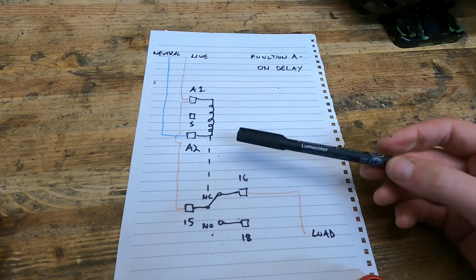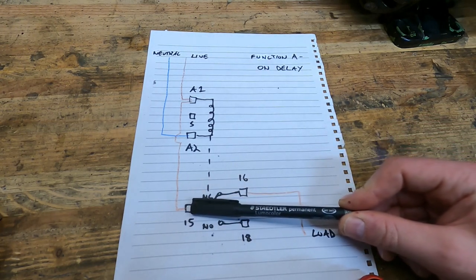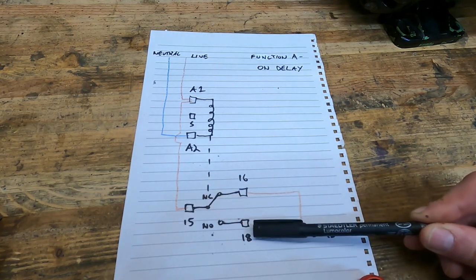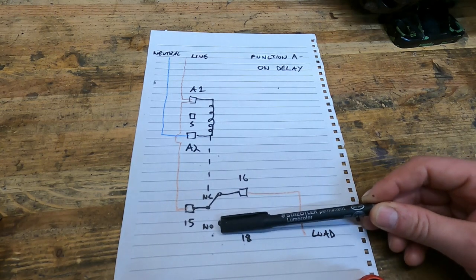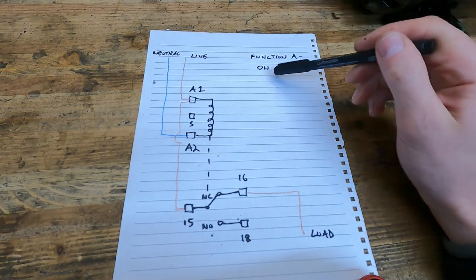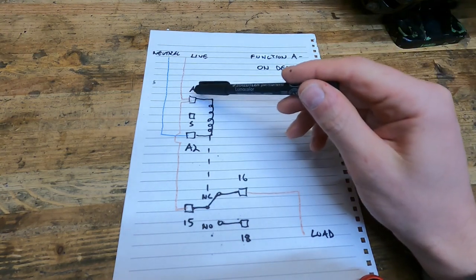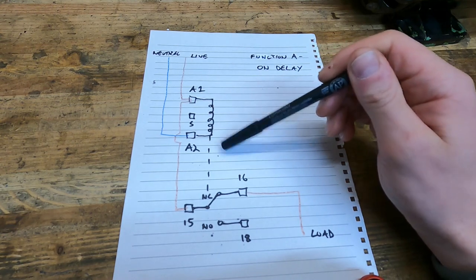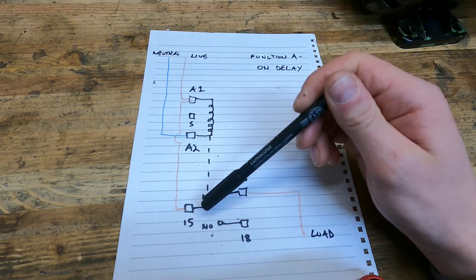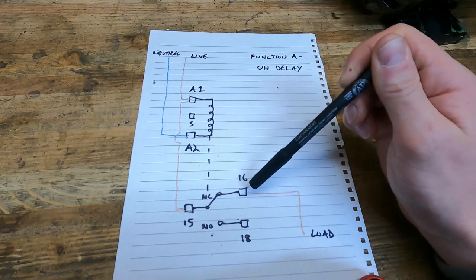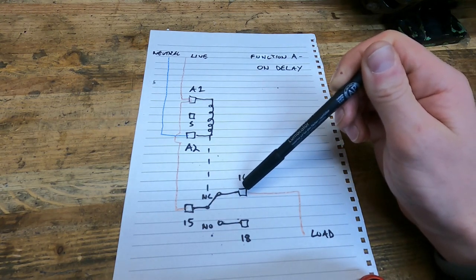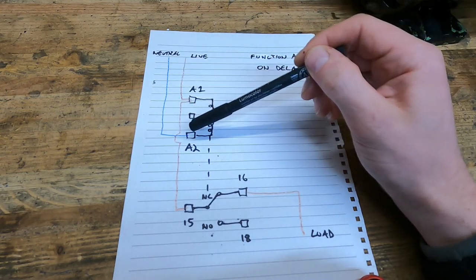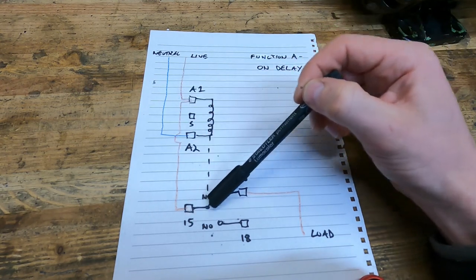Terminals 16 and 18 are on the output side. They get supplied via terminal 15 through a normally closed switch in the case of 16, or through a normally open switch in the case of 18. With function A on delay, when power is applied to the coil via A1 and A2, there's a delay of a specified time period before the relay actuates the switch.